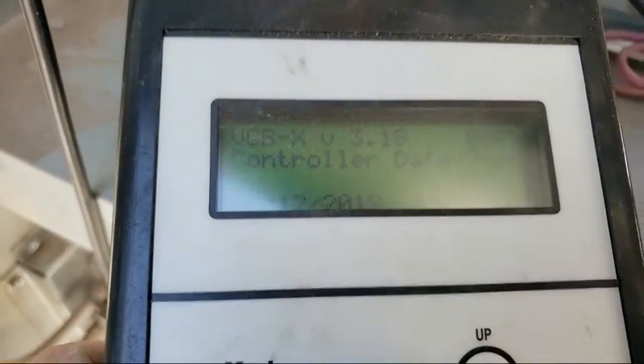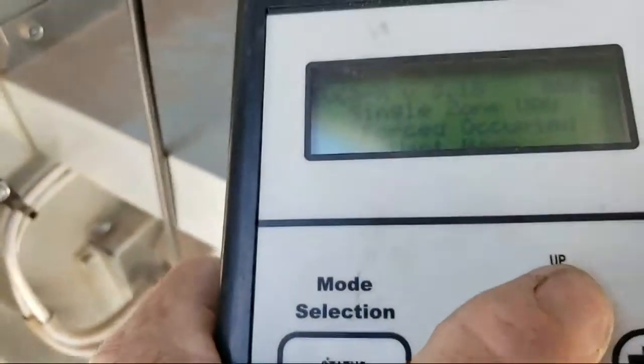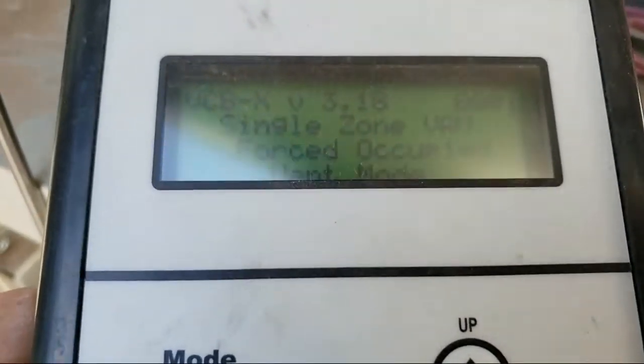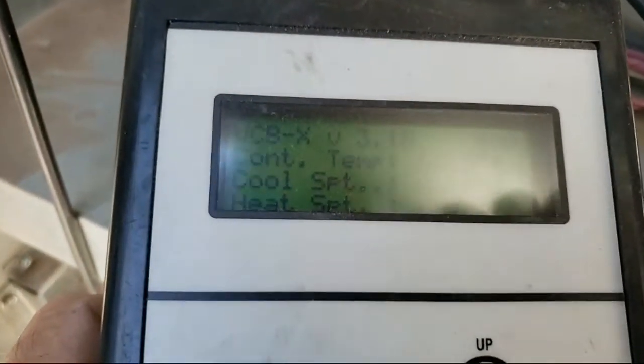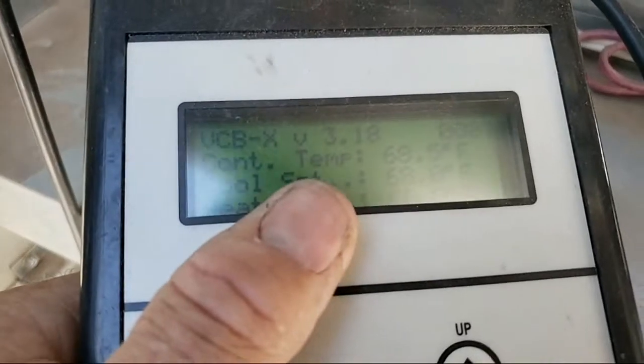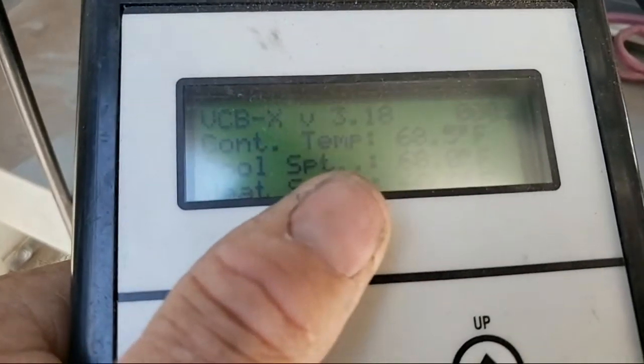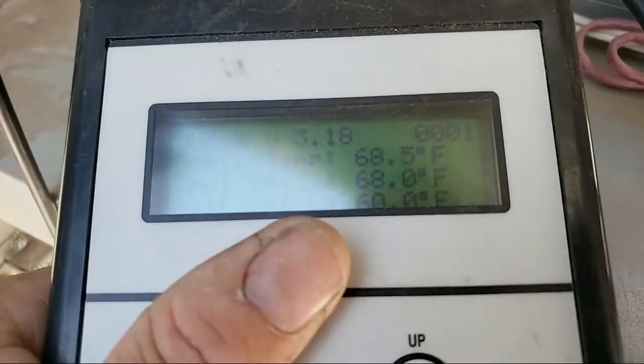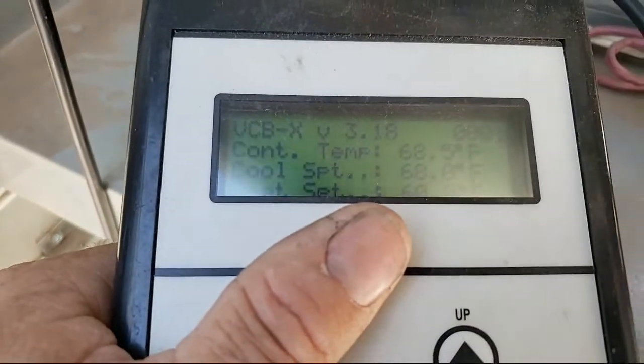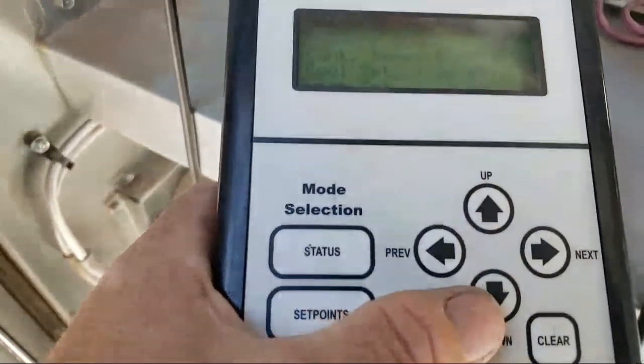Identifies VCB-X controller, which is what that is. No date held. And right now we're running in vent mode, which is great. And there's my control temperature 68.5 and my cool set point 68. So we're not far enough above yet, I guess, to go into cooling, but it should be real quick. Heat set point for 60.